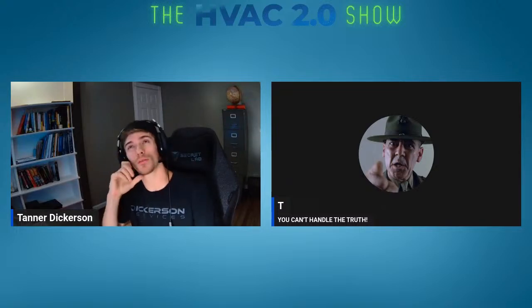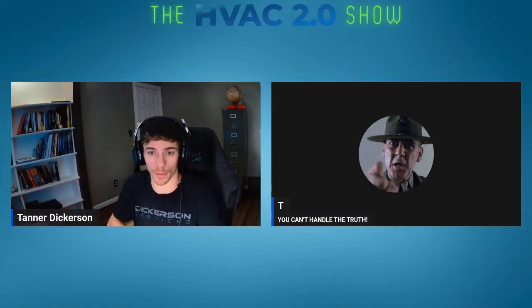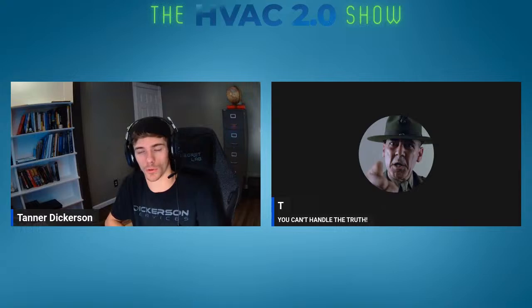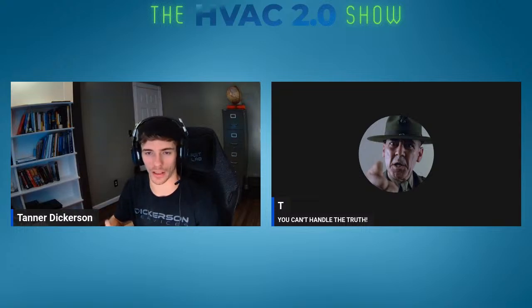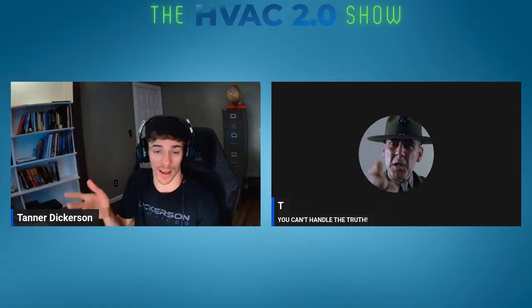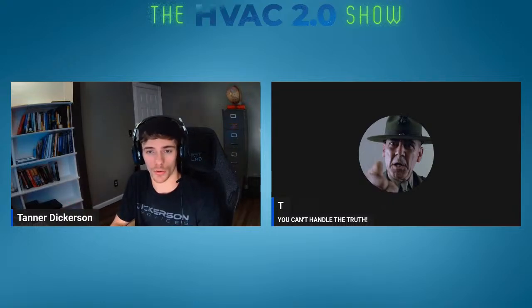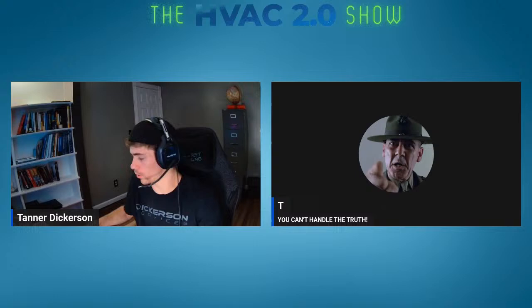Let's see, what would it be? I mean, probably. Because really all you need is a probe kit, which would be 9 probes I think: 2 pressure, 2 line temps, 3 air temp probes, and for static pressure, 2 - though most people only use 1 gauge for static. Fieldpiece and some others have a single port where you need 1 for return, 1 for supply. But really, 8 probes is all you need, and you can do a MeasureQuick report.